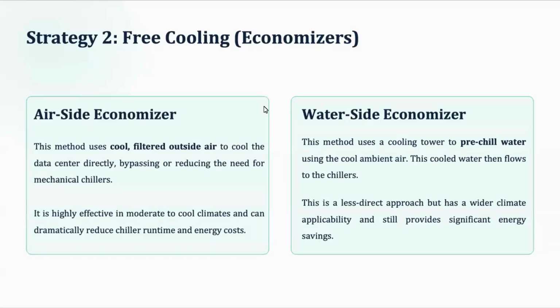As Srinivas sir was mentioning, this can happen in two possible scenarios: one during the winter months, and one during the cooler evenings or cooler nights. When the outside air temperature is very low, that air can be directly supplied into the data centers without mechanical cooling. This will have a huge impact on energy performance, because once you bypass mechanical cooling, the energy used by compressors is completely eliminated. That is a very huge thing. There will be a slight penalty in terms of fan energy, but that is much less compared to the energy saved in compressors.